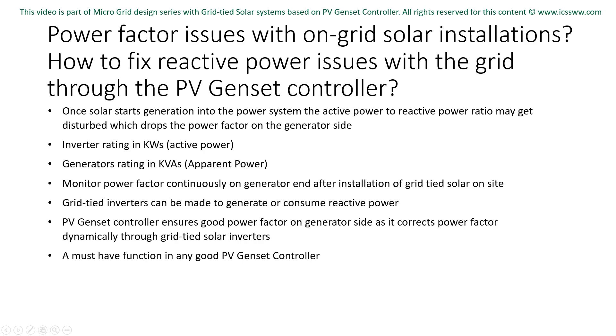Grid-connected inverters can to some extent be made to dynamically generate or consume reactive power in order to correct the power factor on the generator side. However, depending on the power factor setting of the inverter by the controller, it may affect the amount of power generation in kWh, which is mostly insignificant against the fuel saving one gets from such a microgrid. The power factor on the generator end must be strictly monitored once grid-tied solar is installed. Tuning parameters of the PV genset controller or microgrid controller must be reviewed to rectify such issues. PV genset microgrid controllers must always have a power factor correction function built into them, handling it dynamically by correcting the inverter's power factor in leading or lagging condition.